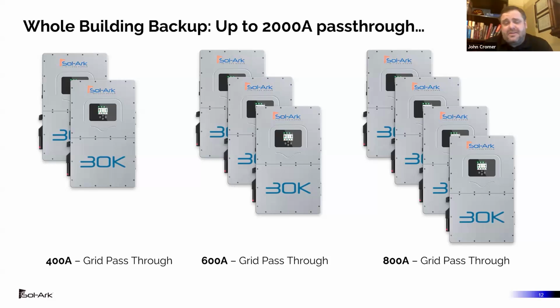You might be implementing industrial load control. And we're going to talk about the design strategy for this pass-through capability. Just as a starting point, what I would recommend is go to your minimum project size with the grid pass-through capability. That might be 2 inverters for 400 amps. And then just add at least 1 more inverter for a little bit of risk mitigation. And in the commercial line we go up to 10 inverters in parallel. So absolutely, it is possible to do whole building backup by going into larger inverter stacks.